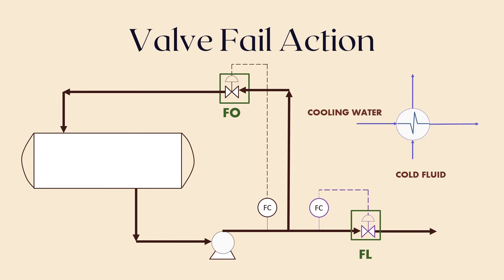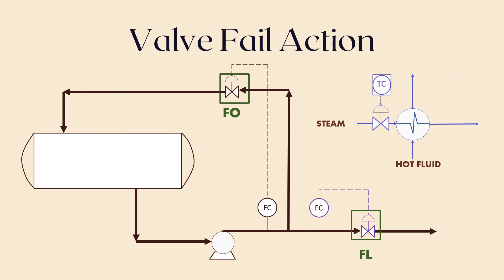Another example of fail open position can be in a water cooler. If the instrument air is cut from the control valve controlling the water flow, we would need to ensure that the hot fluid will still be cooled, so we shall consider the valve to be fail open as this would be the fail safe position. However, if the fluid is heated by steam, the case would be different — if the valve was left to be fail open, overheating the fluid would be a safety issue in most cases. That's why in this case the valve would be fail closed.